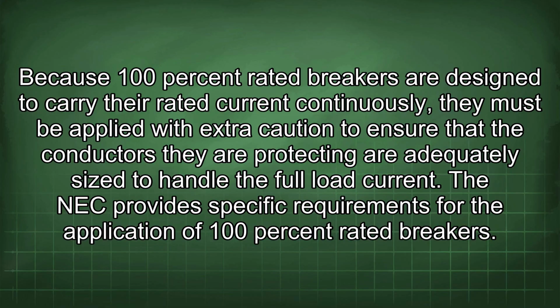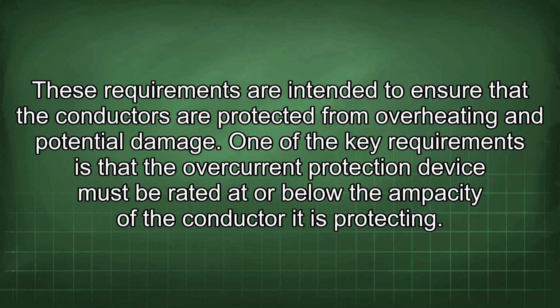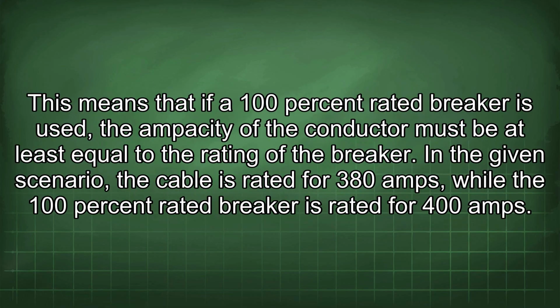The NEC provides specific requirements for the application of 100% rated breakers. These requirements are intended to ensure that the conductors are protected from overheating and potential damage. One of the key requirements is that the overcurrent protection device must be rated at or below the ampacity of the conductor it is protecting. This means that if a 100% rated breaker is used, the ampacity of the conductor must be at least equal to the rating of the breaker.